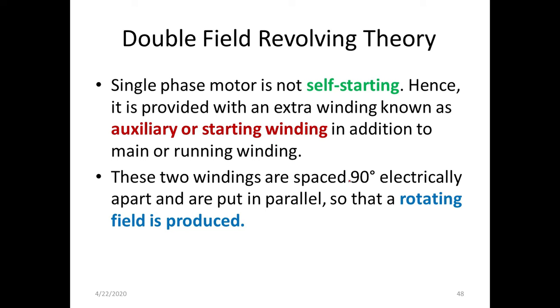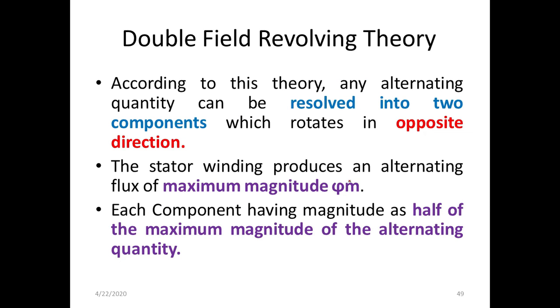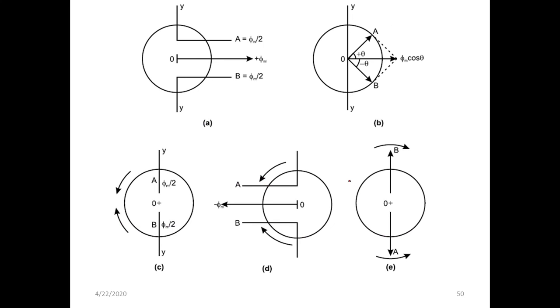As I already told you, it is not self-starting, so we need an extra winding to start. That extra winding is called an auxiliary or starting winding. We already have a main winding. These two windings are placed 90 degrees electrically apart from each other and put in parallel so that a rotating field is produced. This is the one line concept behind double field revolving theory.